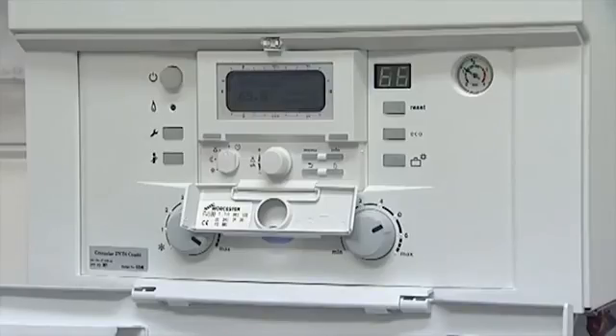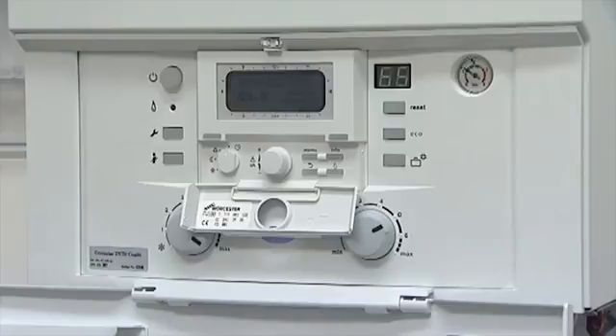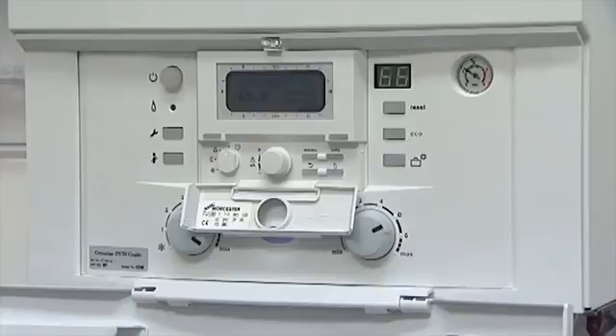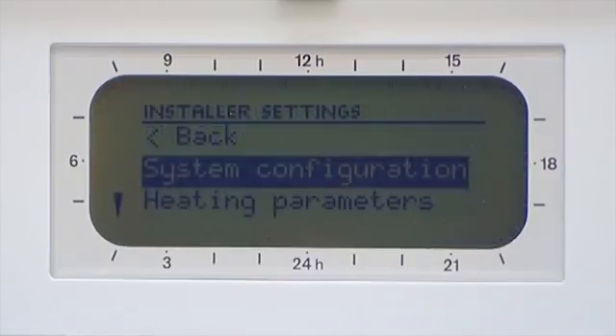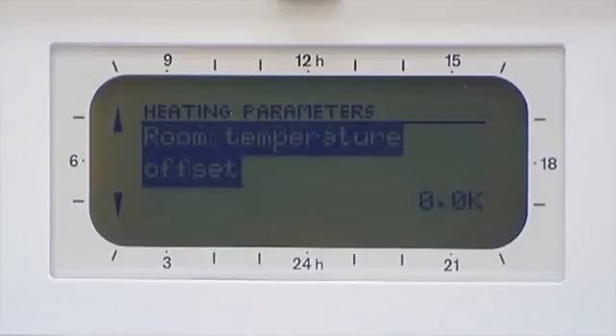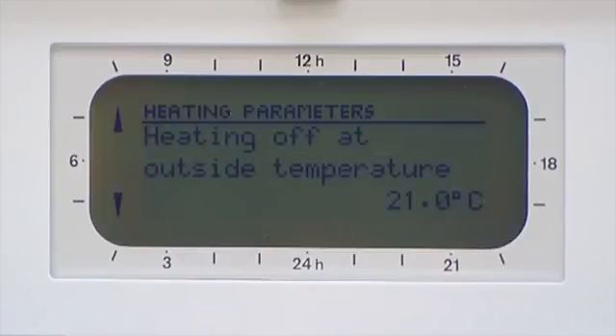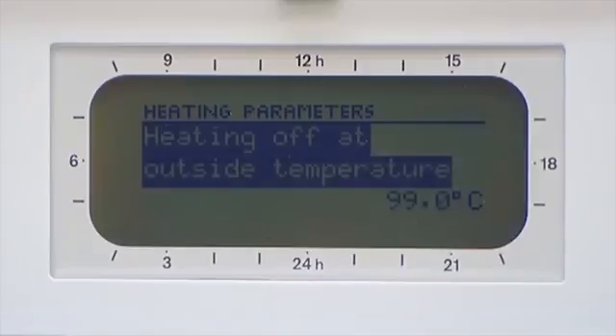If your heating is not coming on, it may be because the outside temperature is above 20 degrees Celsius. If this is the case, the factory setting will prevent the boiler from turning on the heating. It is possible to change this temperature to between 20 and 25 degrees Celsius, or disable it by setting the temperature to 99 degrees Celsius. Press and hold the Menu button for three seconds. Scroll down to Heating Parameters and press OK. Scroll down to Heating Off at Outside Temperatures, press OK, then using the control knob increase the value to 99 degrees Celsius. Press the Menu button to return to the home screen.